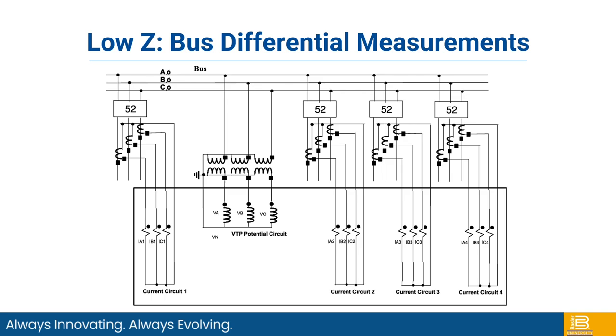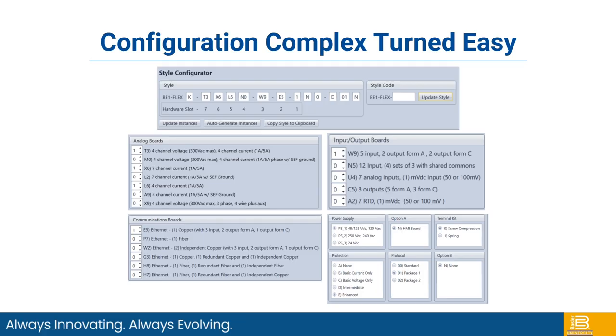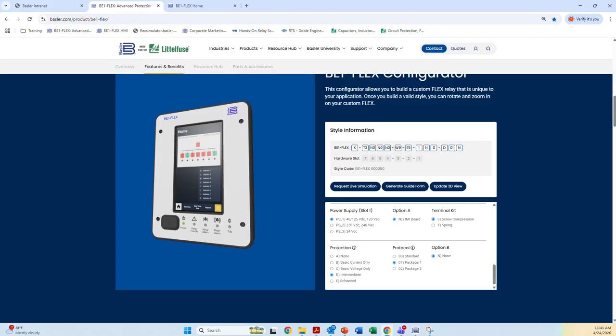So here is our low impedance bus differential application. You've got the main breaker here with three-phase CTs. You've got your three-phase PT, so you can have metering for all of these different breakers. And then you wire in the 3 feeders. So again, you use the configuration tool to make your selections. Again, we'll go through that particular for this. We'll refresh the website here.